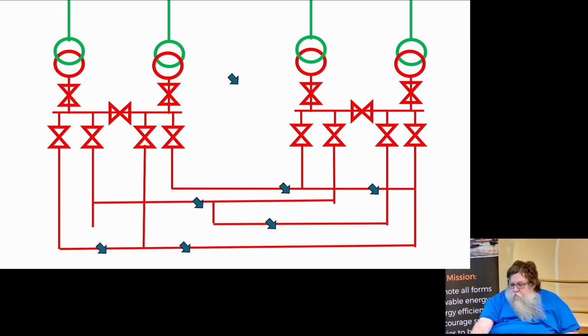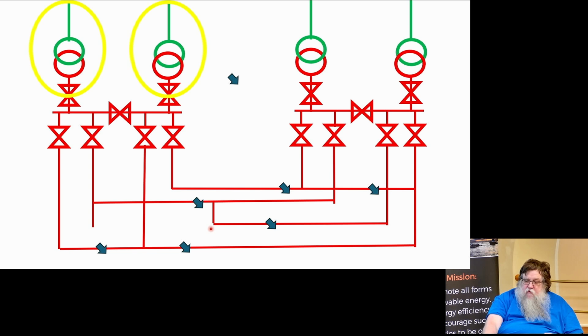So this might be a system that we have where we're looking at 12 to 60 megawatts. It's represented by 2 primary substations, one here and one here. And then the 11 kV feeders, they're interconnected and they've got open points. So all these open points are there, and each circuit is fed from one circuit breaker back at a primary substation. If we get a fault that affects one of the transformers at a substation, then say it's this one, this transformer can supply all that load and go to all the open points. And if need be, if the load can't be sustained long term by this one transformer, we can move these open points from here to a different location.